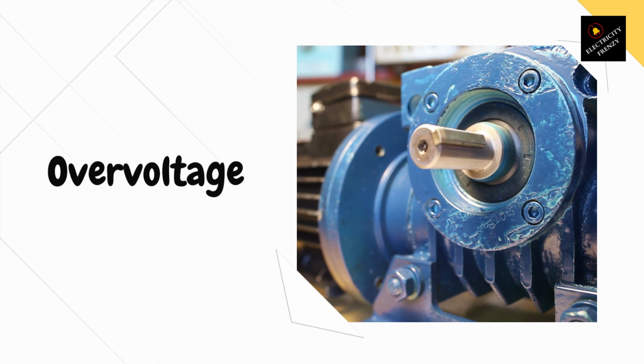Overvoltage can indeed lead to motor insulation failure, which can then result in a short circuit. The excessive voltage can cause the insulation material to break down, compromising its ability to insulate the motor windings effectively. When the insulation fails, it can lead to short circuits within the motor, which can cause damage and ultimately contribute to motor burnout.